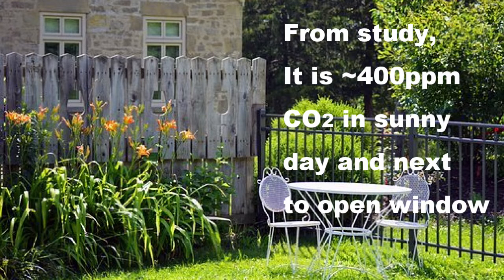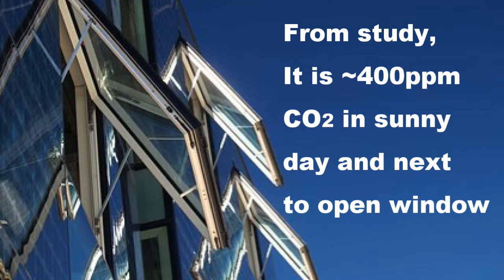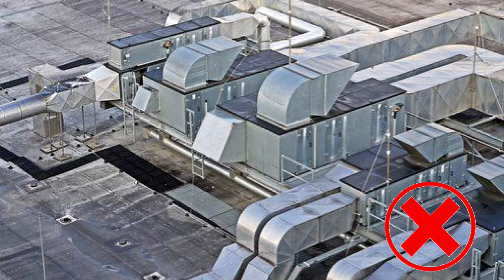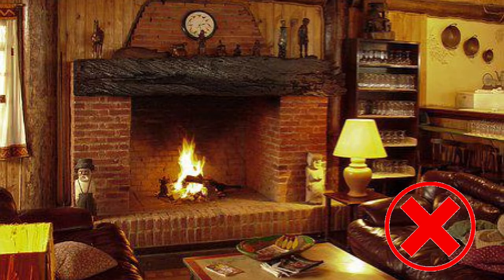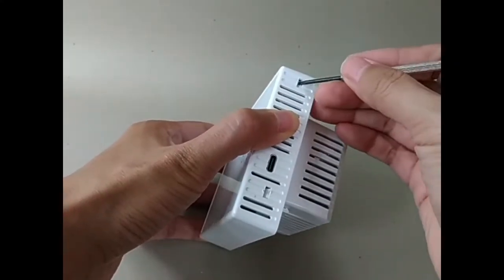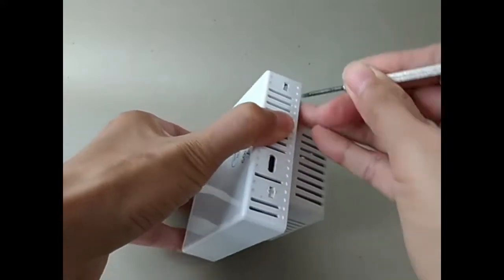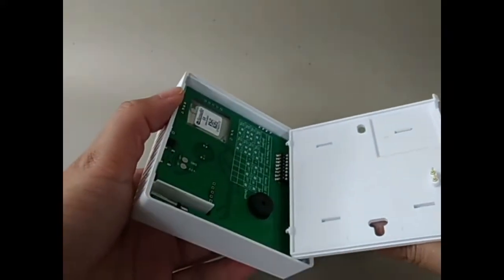Please calibrate the meter on a sunny day with good fresh airflow where the CO2 level is around 400 ppm. Don't calibrate it in places crowded with people or close to high CO2 exhausting, such as outlets or fireplaces. Using a flat screwdriver, press in the two securing clips at the bottom of the monitoring housing, whilst easing it away from the mounting plate from the bottom.